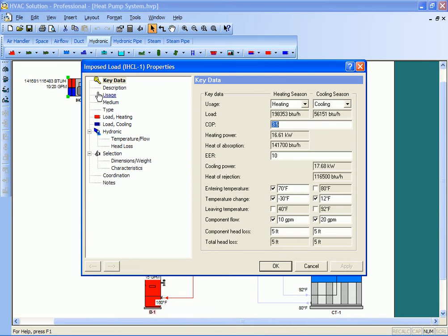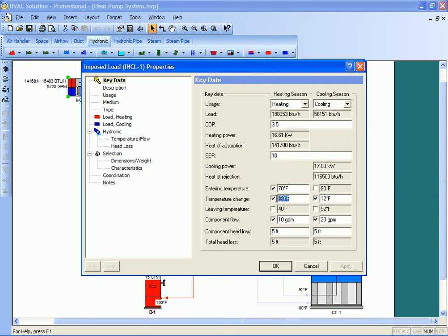Basically what I've done is I've set a flow in both the heating and cooling seasons. I've set a delta T, and then on the boiler, or on the heating side, I've set a 70 degree entering temperature.